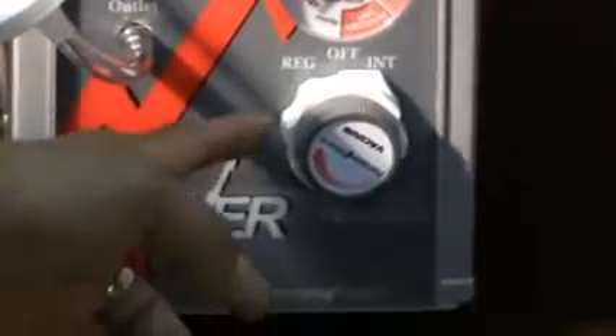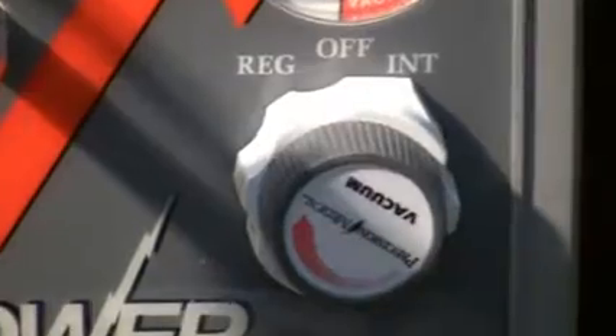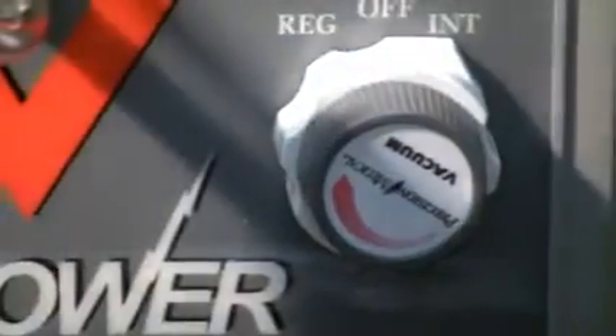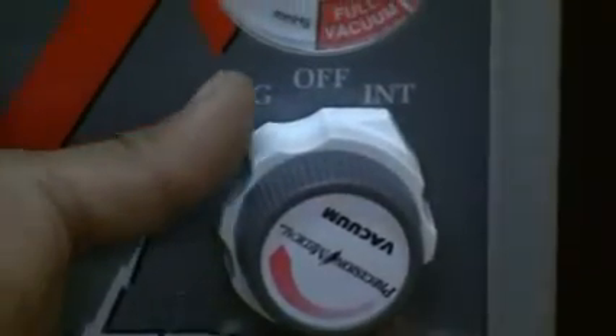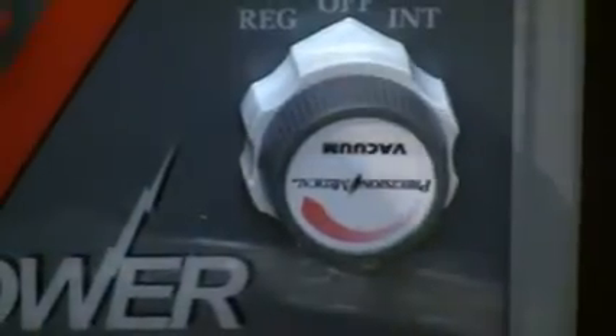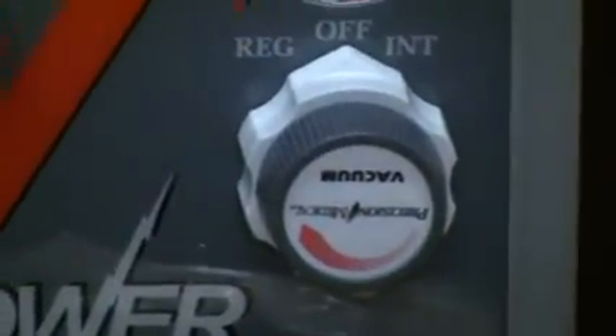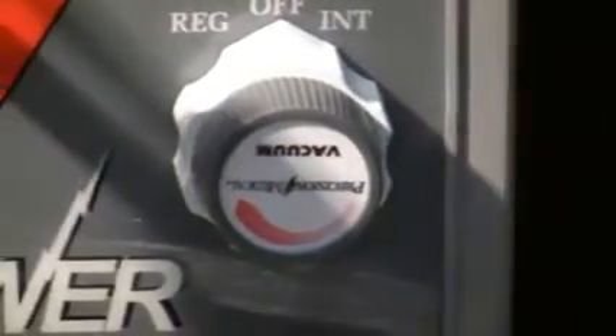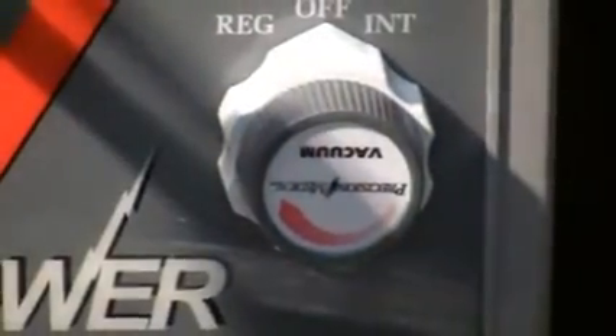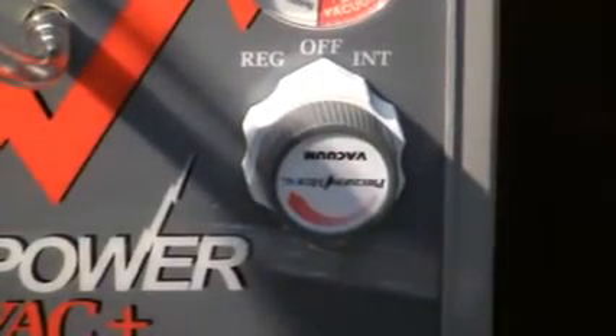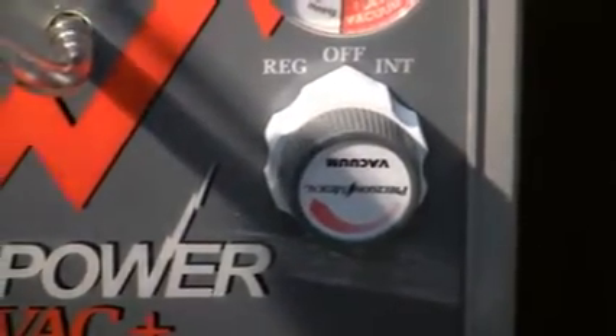You do have dual knobs here, two knobs directly located underneath your vacuum gauge. You have a white knob, which is located on the rear, and that is your vacuum mode selector. The white knob, when selected, will select your vacuum mode. You have a regular vacuum mode, off, as well as INT for intermittent. With your vacuum mode selector in the off position, we stated there will be no vacuum.